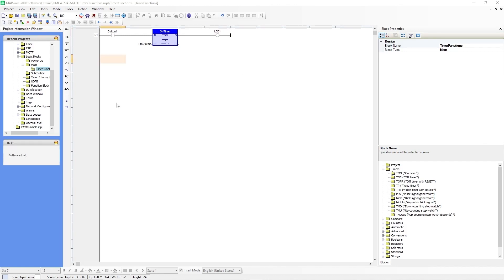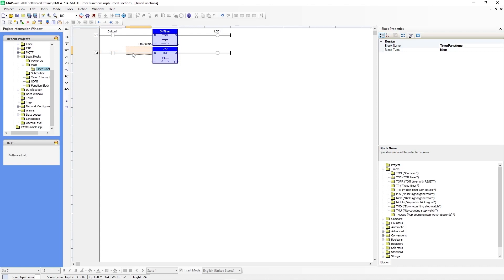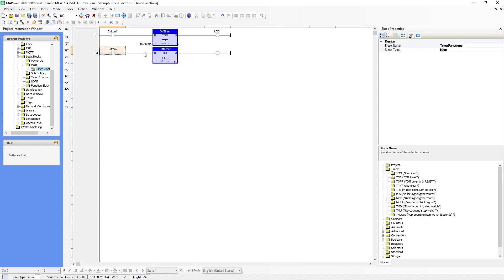Next will be the TOF or off timer. Let's insert a new rung. Over to the right, I'm going to grab the TOF off timer and drag it over. Let's call this off timer. The input coil will be Button 2. The preset time will also be 5000 milliseconds, and you do not need to enter anything into the elapsed time, which is also the time register. For the output coil will be LED 2.